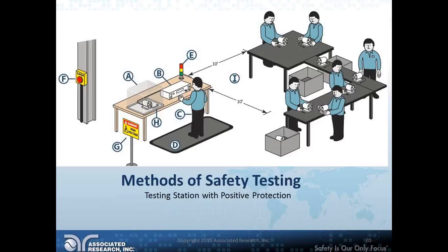E is a signal warning light, what we call a signal tower light that you can wire up to these stations. For example, when a test is running, a red light goes on. When the instrument is idle or off, a green light goes on to show everybody in the immediate area that testing isn't going on right now.